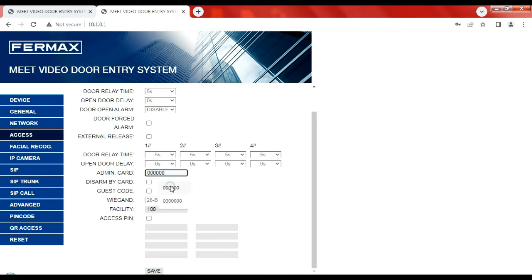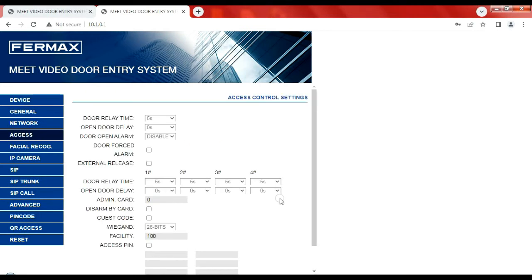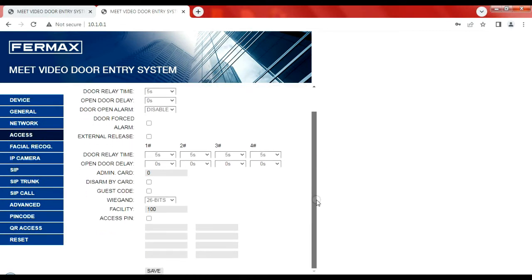Admin card. The device itself, the panel itself has a built-in MiFare reader, and it can work in a standalone fashion. So if you put in six zeros in this field here and then press save, what that means is the first MiFare card that's presented to the reader becomes an admin card, becomes a master card. And you can use that to add further cards down the line. So it's useful if you're not managing the site, the end user's going to manage the site. It's useful for them. If they want to add more users, they can simply use a master card to add more users.